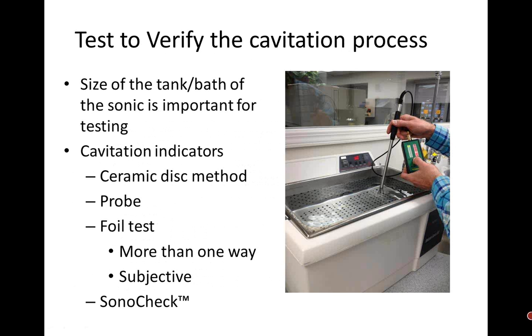So, where are ways to do cavitation? And again, there's a difference between cavitation and checking the cleaning. You want to make sure there's cavitation. Traditionally, and I'm going to give my age here, and it's not used much, there's a ceramic disc test, and that's where you would put certain ceramic discs and you would put lead on them and you drop it in and run a certain amount of time and pull it up, and then you'd have a chart to compare it to. It was subjective, but it was also how hard somebody put the lead on it. I'm pretty intense, as some of you might know me. I could have put more on and not enough. So again, that is all subjective, but that is something that's been used.